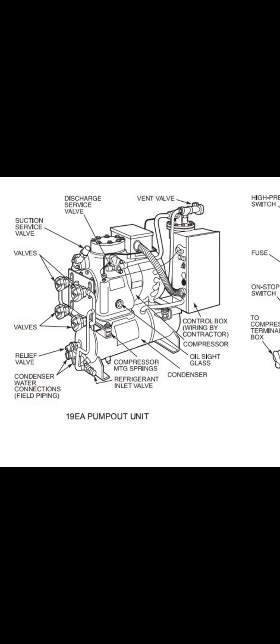Two lines are needed, one for suction and one for discharge, so you can change them. So two flexible hoses, half inch, are needed to reach all chillers. If you pump down or pump out, you need to open the liquid line and continue; on the upper side you can close the valve. Suppose you want to store in the condenser: you put the compressor pump out discharge line to the evaporator, and the suction line in the condenser, and the pump out unit runs. It will give pressurized hot gas to the evaporator and take refrigerant by suction from the condenser.